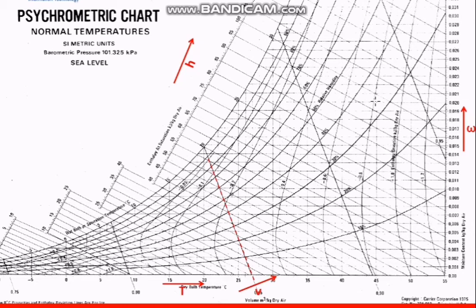To find the dew point temperature from the point at 0.02 and 45°C, we move horizontally to the left, because the humidity ratio remains constant until condensation occurs. Moving left in a straight line, we reach the saturation line — and the dew point temperature here is 25 degrees Celsius. If condensation starts, the process follows along the saturation line.